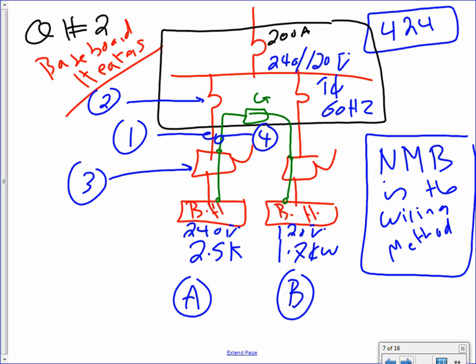NM-B is the wiring method. 424 is the article that talks about baseboard heaters. I have the same panel, 240/120. By the way, Derek, when you put a panel, if you don't put the amps of the main panel and the voltage and what phase and what frequency, you have no clue what we're talking about. It's like, what do you drive? I drive a car. Hey, what type of car, right? So when you say a panel, it doesn't mean much.